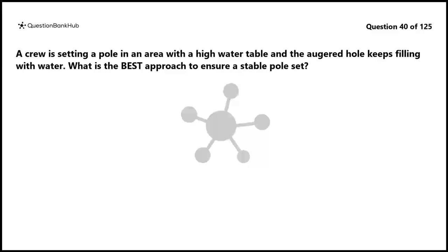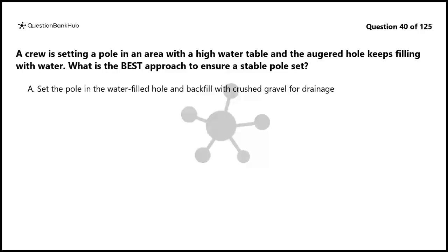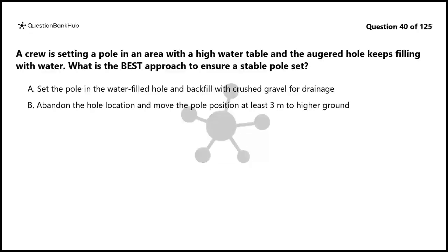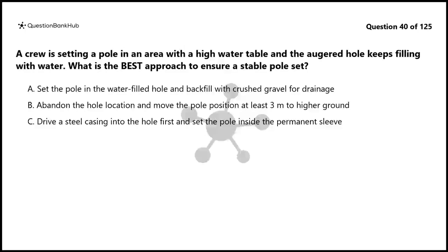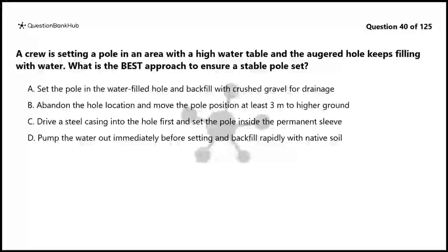Question 40. A crew is setting a pole in an area with a high water table and the augered hole keeps filling with water. What is the best approach to ensure a stable pole set? A. Set the pole in the water-filled hole and backfill with crushed gravel for drainage. B. Abandon the hole location and move the pole position at least 3 meters to higher ground. C. Drive a steel casing into the hole first and set the pole inside the permanent sleeve. D. Pump the water out immediately before setting and backfill rapidly with native soil.